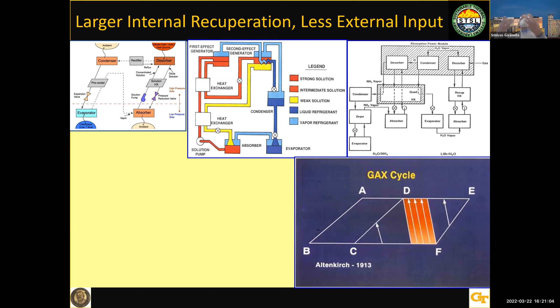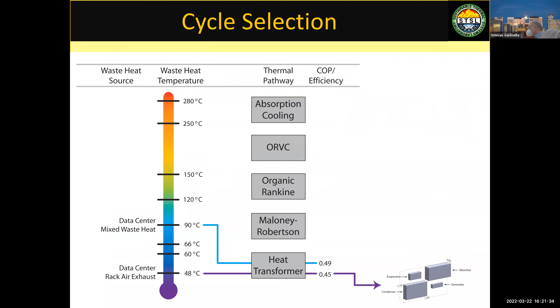We have to match these systems to the kind of heat available, so we came up with a temperature selection chart showing various types of waste heat at different temperatures. Data center waste heat, for example, is actually very cold, so you can use a heat transformer to upgrade it to higher temperatures. A microturbine exhaust comes at high temperatures, so you can design absorption cooling systems. We came up with different COPs for utilizing waste heat that would otherwise be thrown away, for common end users.